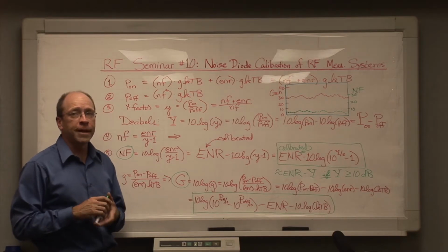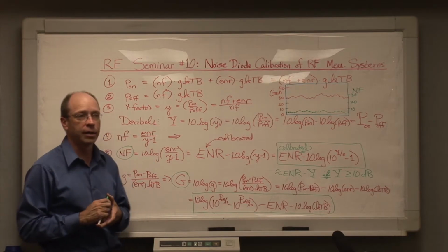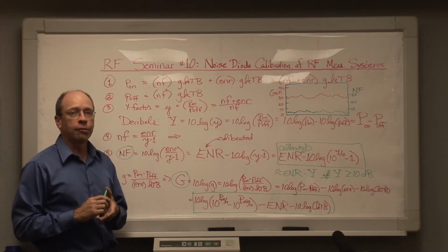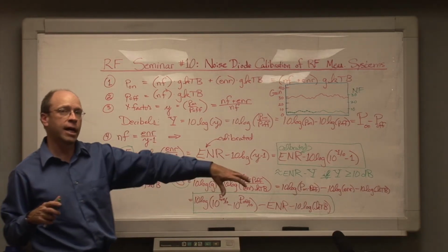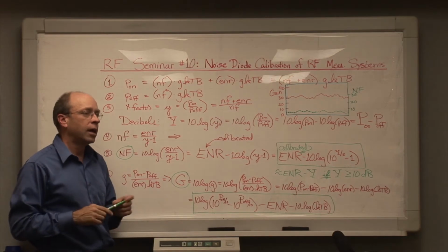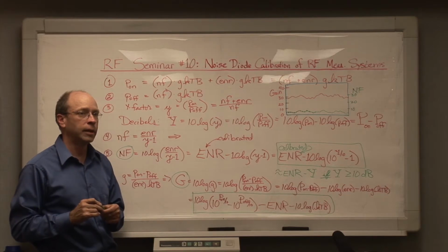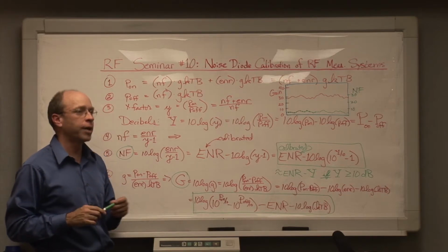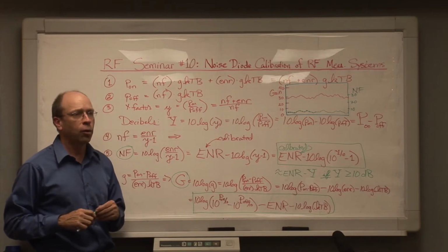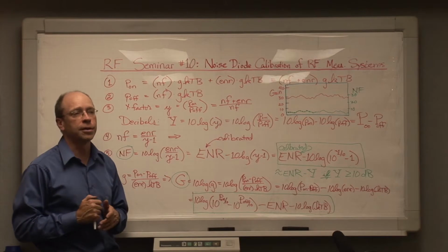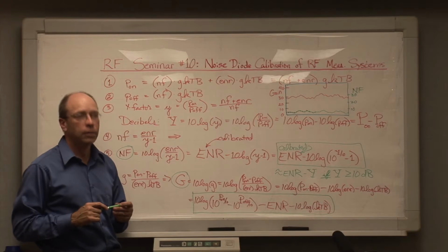Here at ITS, we've actually had a program, or a process running recently anyway, where we've gone to a lot of trouble to calibrate all of our noise diodes that are in our inventory right now against, and correct me if I'm wrong about this, Randy, a noise diode which has itself gone through a rather precise calibration independently. Is that true? Yeah, we're still working on it. And you're still working on it. What would you say the uncertainties are in those noise diode calibrations? I don't know, because we haven't fully developed the system.